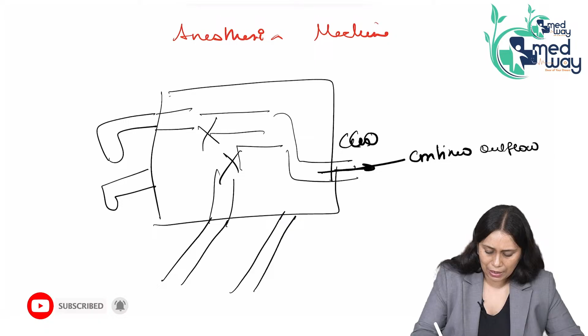Now, this machine has various parts and parts are divided according to the pressure. So, I just want to tell you that let's say this is the anesthesia machine again. This is your cylinder. Now, cylinder has a pressure, let's say oxygen cylinder has a pressure of 2200 psi. When the oxygen comes out of the cylinder, its pressure is reduced and now its pressure is 40 psi. So, from 2200 it became 40.